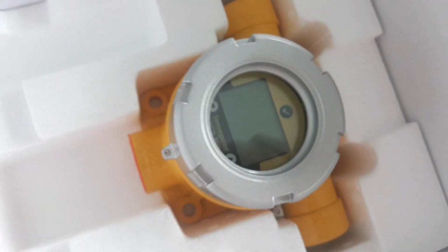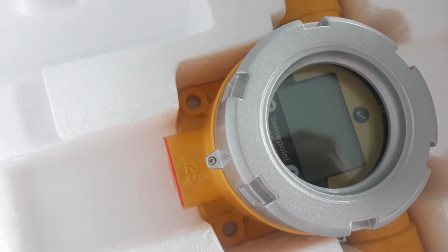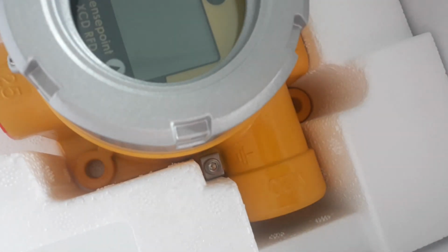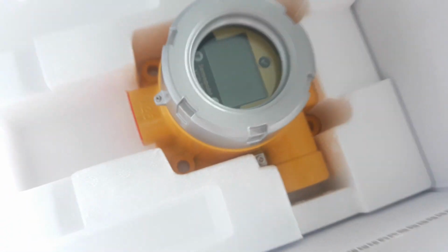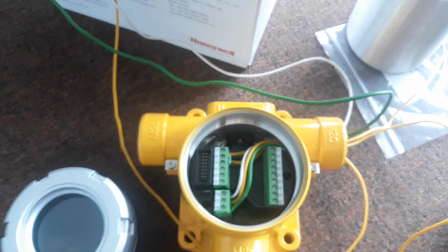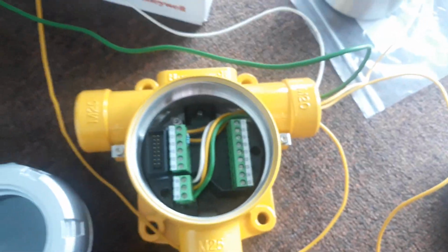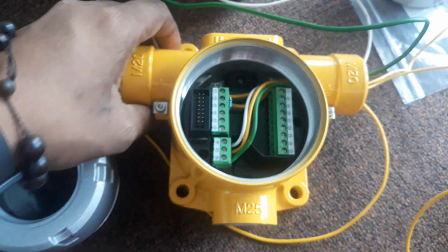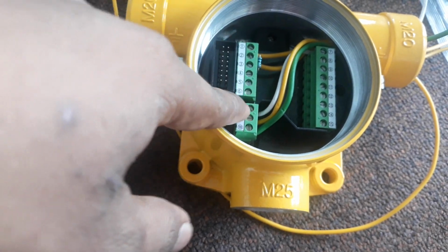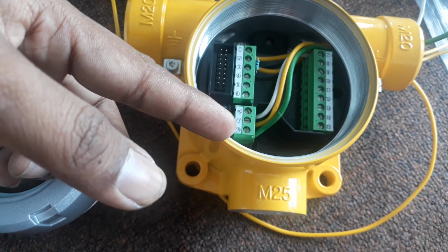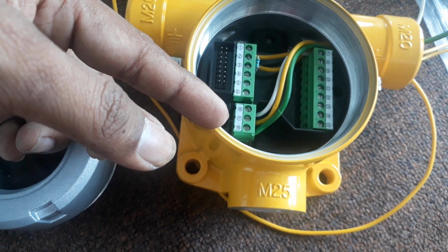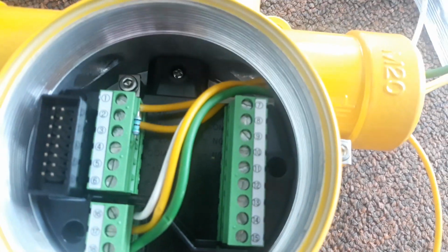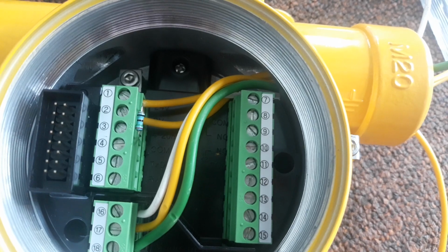And then we got the controller. Here, the yellow color, we have a cable gland, M25 and M20, so you can insert the cable. Okay, I have done the wiring. Here we got the terminal block. You have a power terminal block, and you also have a connection from the sensor to your controller. This one is for the relay alarm, and we also have a 4-to-20 output.